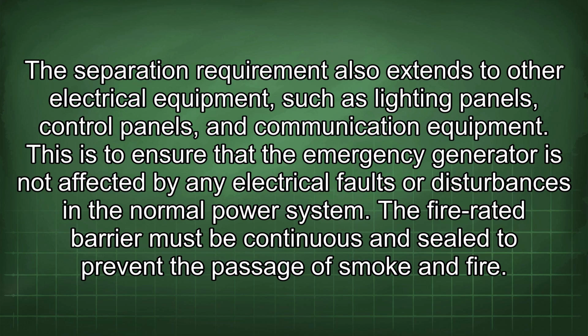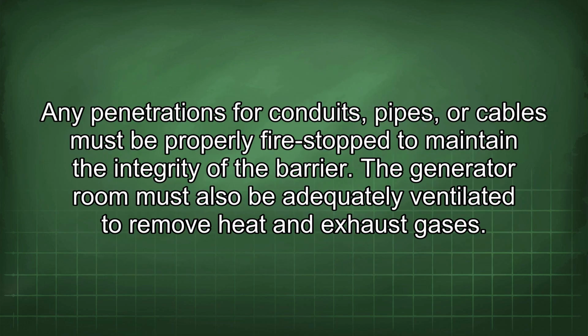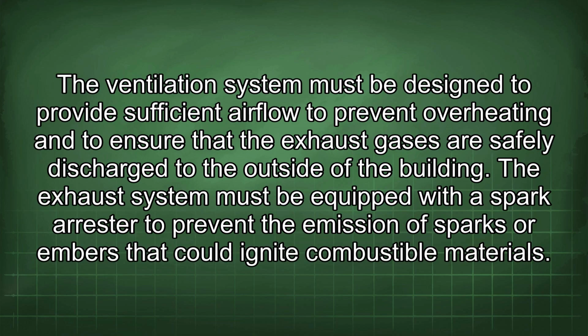This separation requirement also extends to other electrical equipment, such as lighting panels, control panels, and communication equipment. This is to ensure that the emergency generator is not affected by any electrical faults or disturbances in the normal power system. The fire-rated barrier must be continuous and sealed to prevent the passage of smoke and fire. Any penetrations for conduits, pipes, or cables must be properly fire-stopped to maintain the integrity of the barrier. The generator room must also be adequately ventilated to remove heat and exhaust gases. The ventilation system must be designed to provide sufficient airflow to prevent overheating and to ensure that the exhaust gases are safely discharged to the outside of the building.